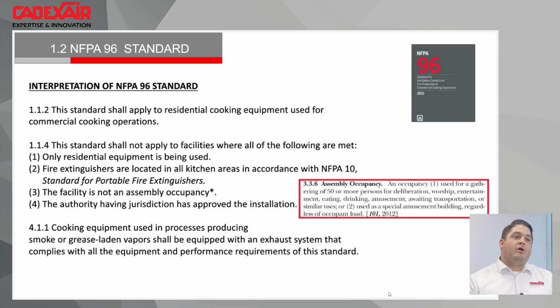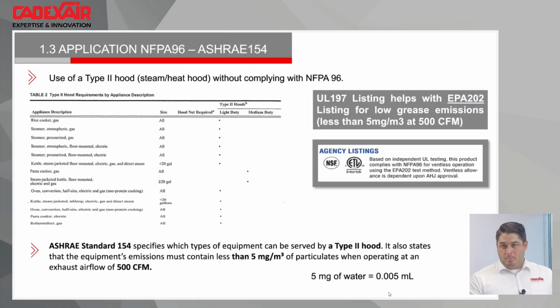As soon as you have to comply with NFPA 96, you need what we call a Type 1 hood, or certified hood, with filters in it, gauge welded ductwork, and an exhaust fan. You also need a full fire protection system for the ductwork, the hood, and the equipment, not the fan, and often makeup air as soon as you're starting to have a bigger system.